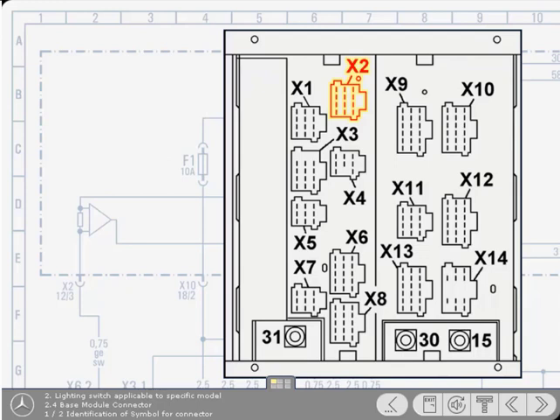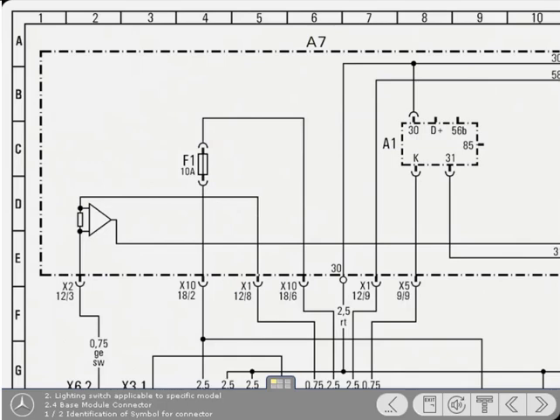The cable leaves the base module at terminal designation X2 12-3, and you already know that the X2 denotes the connector block. The remaining numbers simply explain that it's a 12-chamber connector block and the cable is in chamber 3. Note that although it's a 12-chamber connector block, often not all the chambers are used.